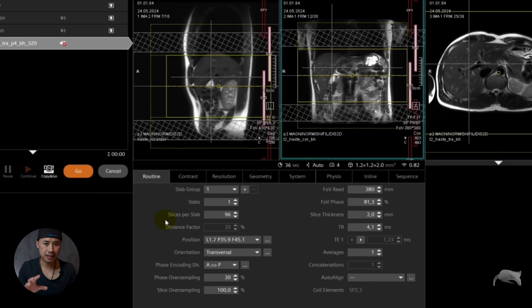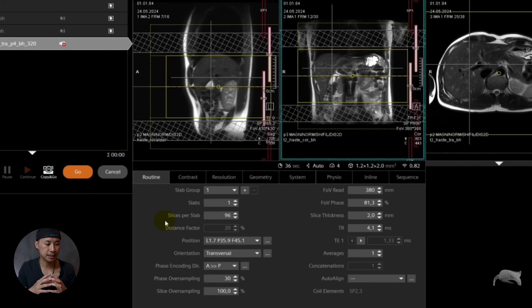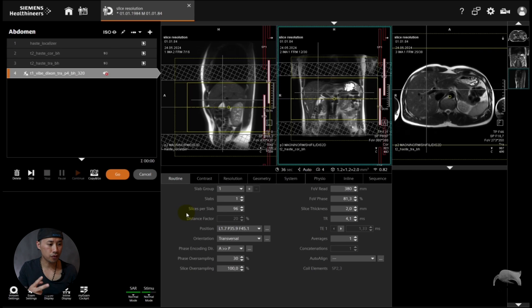The next thing I want to show you on the 3D sequence: remember there are phase oversampling, same as the 2D, so this is AP, so in AP direction. But there's also phase encoding in the slice, in slice direction. That means that this slice is transversal, so you need to think about two things. You can get aliasing folding in transversal direction, which is your slice. You can also get aliasing folding in your phase direction, which in this case is AP.